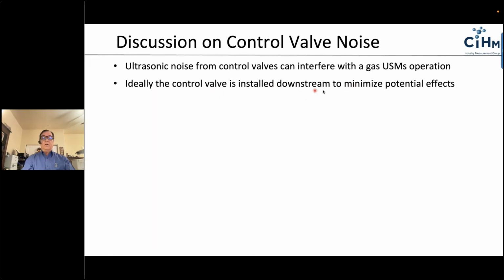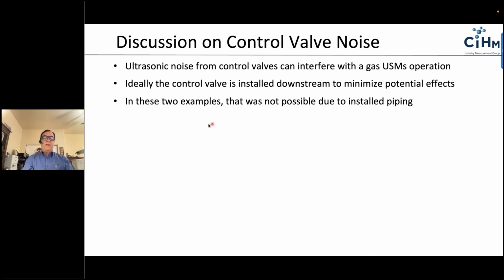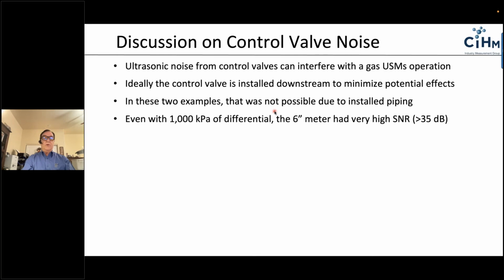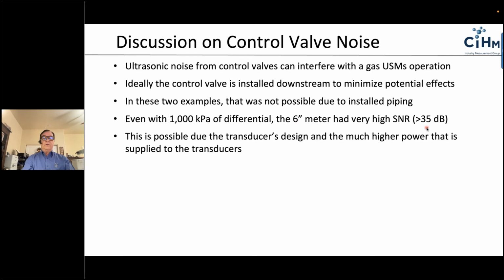Ideally, you'd want to install the control valve downstream of the ultrasonic meter, but in this case, that wasn't possible. So in both of these cases, the regulator was installed upstream. Again, 1000 kPa differential on the 6-inch meter still had a very high signal to noise. The possible reason is the much higher power that's provided to these transducers and the sealed titanium design of the transducer.